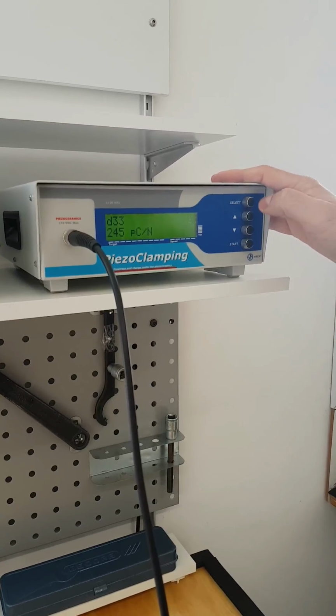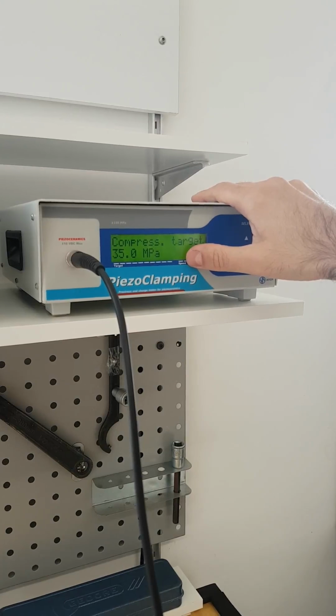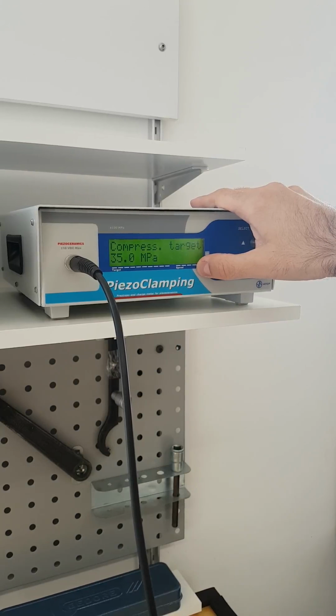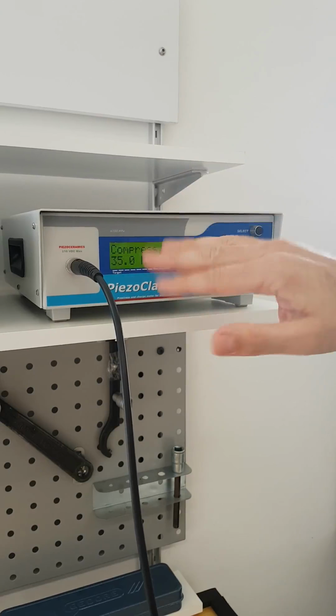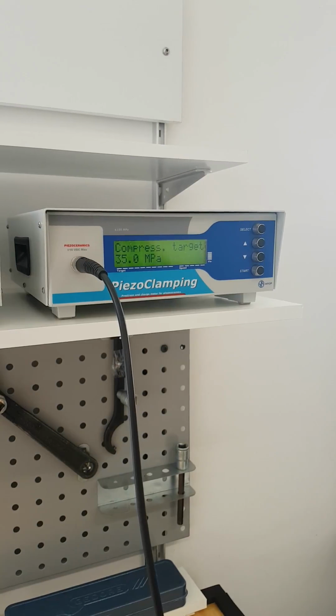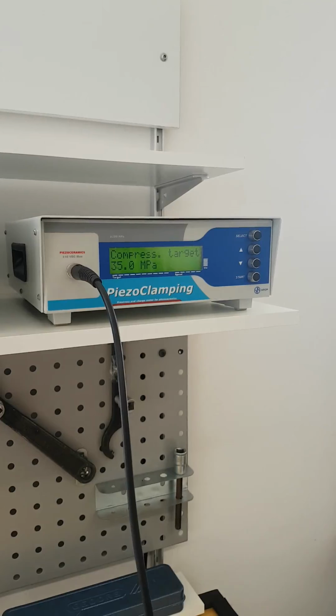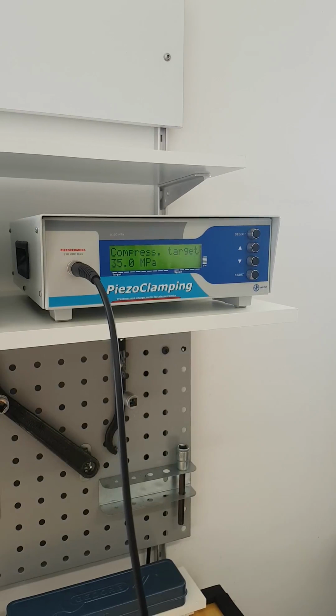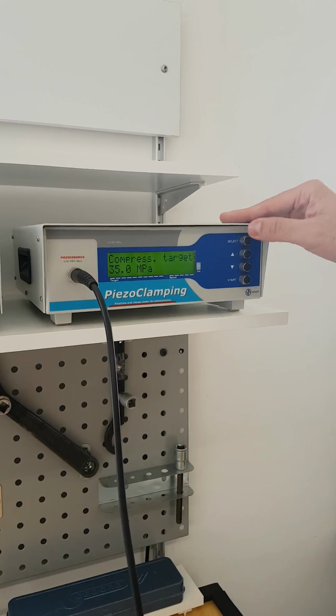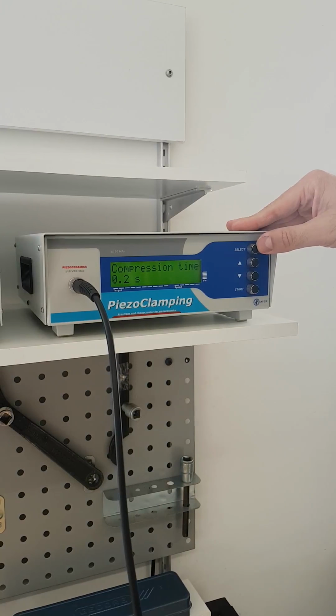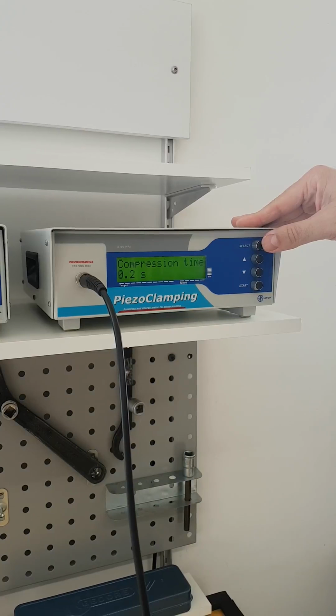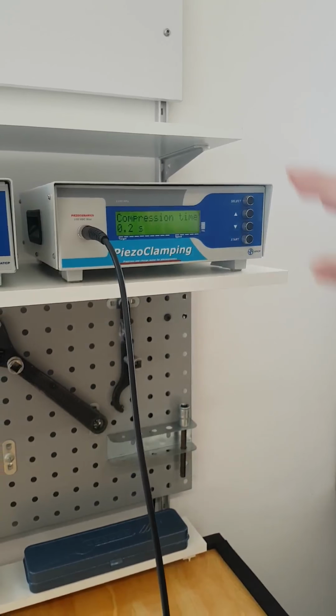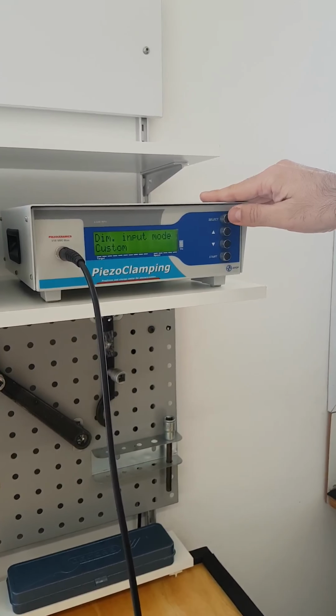And here is the compression target for an ultrasonic cleaning transducer. Usually it should be 35 megapascals, but you can go up to 50 megapascals, no more than that. And the compression time, it's how fast you go. If you go faster than that, the equipment will warn you.